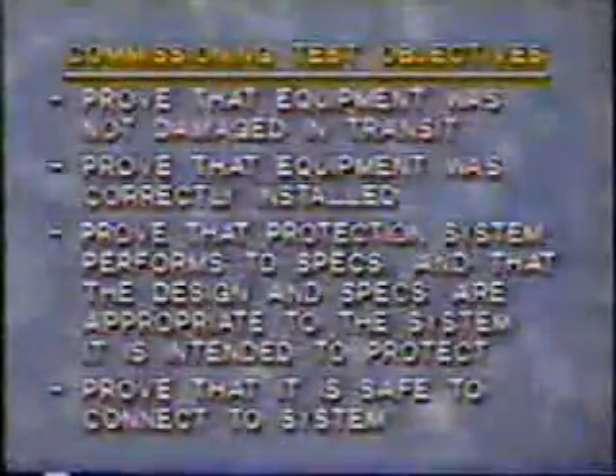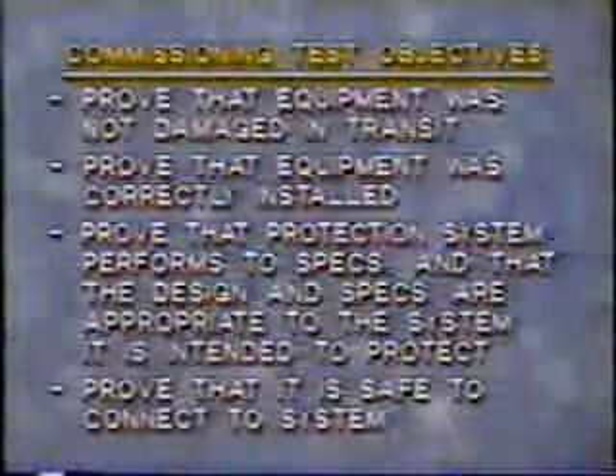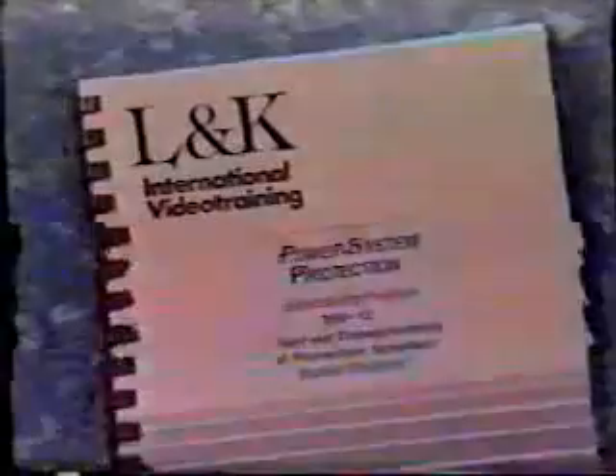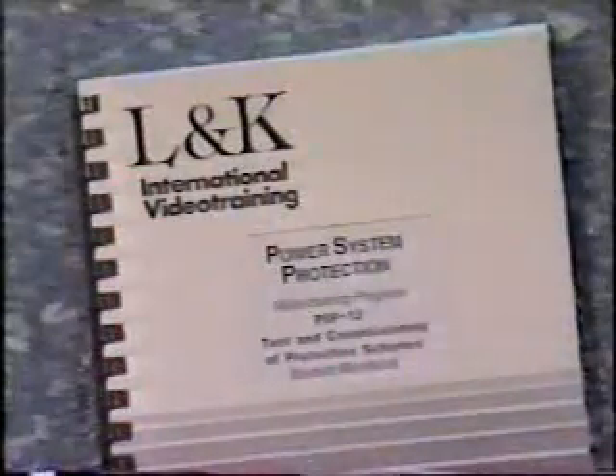The objectives of the commissioning tests are to prove that the equipment has not been damaged in transit, prove that the equipment has been correctly installed, prove that the protection system performs according to specification, and that the design and specifications of the protection system are appropriate to the system it is intended to protect, and prove that it is safe to connect the new installation to the power system. A typical list of commissioning tasks for all equipment is included in your workbook. Take time to study this list in detail.